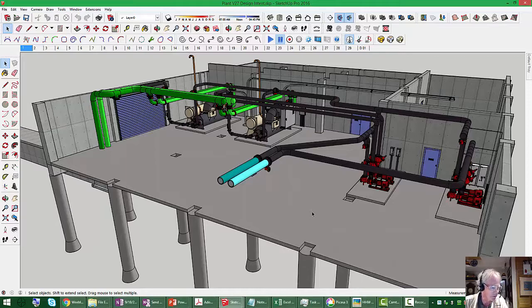If this was a constant flow plant, there's a pretty good chance there'd only be one pump for each chiller, or certainly there wouldn't be two piping loops. And you can see from this perspective that there are two pairs of pumps. If you start looking at what the pipes from the pumps do, for instance, this pump, the pipe drops down, goes into the pump, goes out, runs through the chiller, comes out of the chiller, comes back, picks up the other chiller, comes back to a T in the pipe, and then the T goes to the other pair of pumps, and also to a pipe that reconnects to the suction side of the pump we're thinking about.